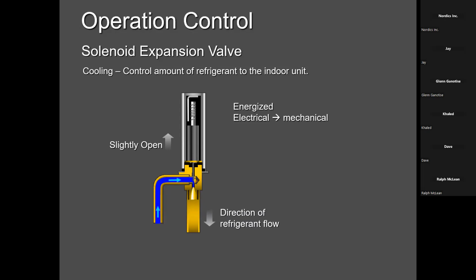So there you see the EEV is slightly open, and then as you are asking for more cooling, it opens even higher, and then here we are probably at max. So keep in mind, guys, this electronic expansion valve talks constantly with the compressor, with the outdoor fan, and a bunch of sensors. Okay, guys? So when the sensor at the indoor unit is asking for more refrigerant, this guy will respond, and obviously the compressor will also increase its frequency. If the compressor is not increasing its frequency, definitely there's something wrong. They are not talking to each other well, and something needs to be figured out.